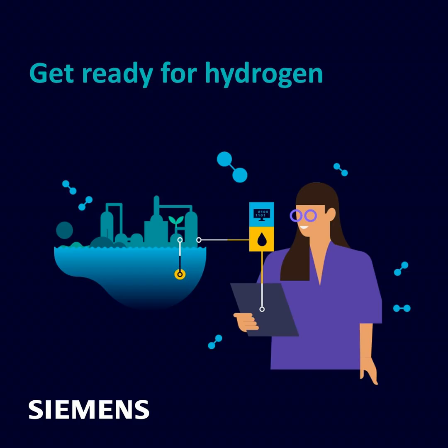This ensures that both the process engineer, who knows what needs to be done, and the automation specialist who has to program it somehow can clearly see that all these connections are correct and that it is well documented that the plant operates in a safe condition. Because, for example, you should not simply shut down an electrolyzer abruptly, because if you did that, then it can potentially reverse and suddenly act like a fuel cell in an already dangerous situation.